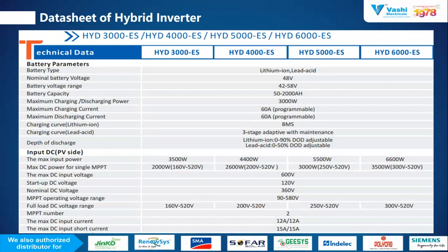Nominal battery voltage is 48. Its capacity is 50 to 2000 Ah. It means you can scale up to 2000 Ah. It's compatible with the BMS, meaning you can connect the battery, CT connection, RS485 connection, and NTC, meaning negative temperature coefficient, especially for the lead acid batteries. These are all the features that we have in the single phase inverter. I repeatedly say CT connection, RS485 connection, NTC connection for the lead acid batteries.